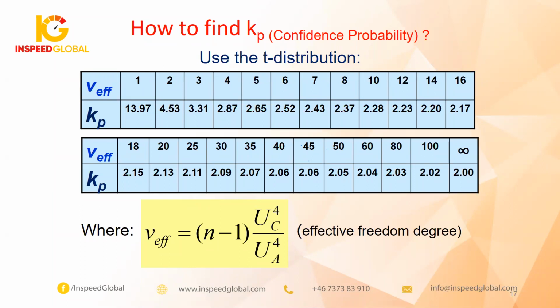As you see, V effective. Also, how to get V effective? I need to get V effective, and use these tables to get Kp directly. So how to get V effective? You can see in this very simple equation, V effective is equal to n-1, and as you see, UC and UA. UC is U combined, and UA is repeatability, or uncertainty of type A. Of course, you have UC from the table, okay? And you also have UA from the table. And n is the number of readings, as you know, 5, 6, 10. So directly you can get V effective.